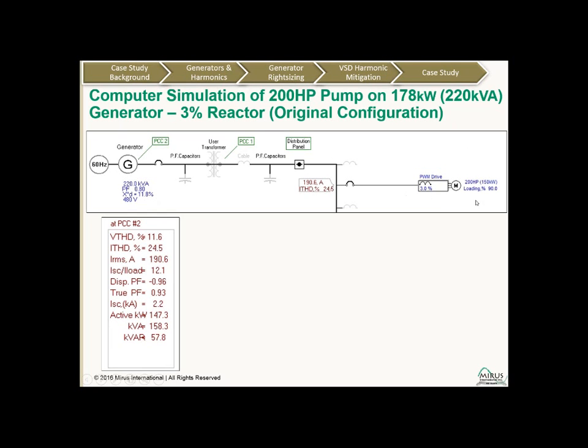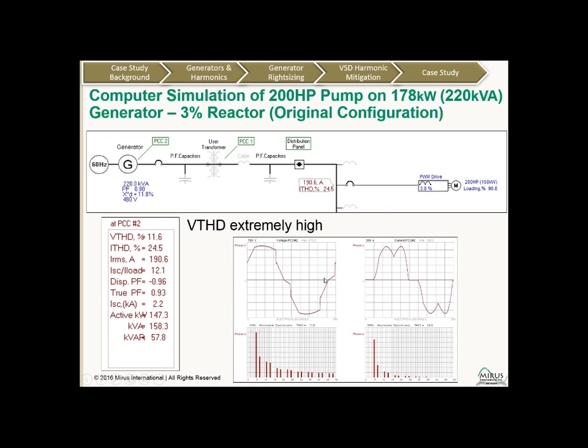And then there's the VFD. This VFD was equipped with a 3% line reactor. It's 200 horsepower, and to get the rated flow of 240 barrels per hour it's running around 90% loaded. So we get 24% current distortion, 11.6% voltage distortion. You can see the distortion of the voltage waveform, flat topping, a lot of harmonics. This is a scale of 10%, and there's our input current, the double humped.